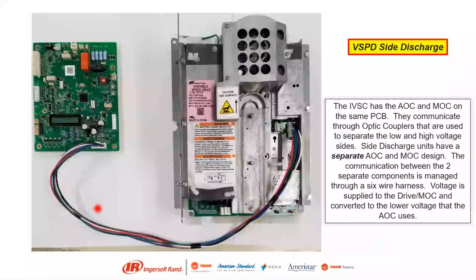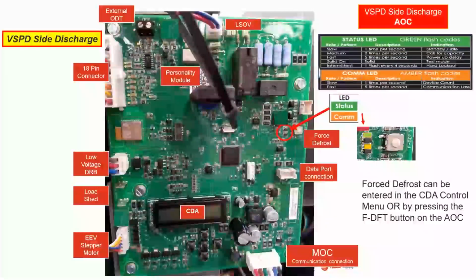Sometimes we get a bad harness, so we want to always double check these connections. With the power off, I like to pull these connections, put them back in, and then push the wires all the way in to make sure we got a good solid connection. Here's our board. Here's our CDA, EEV stepper motor, our voltage. So we'll have test pins right there, 18-pin connector with all of our sensors. I'll go into that. Here's our personality module, our switchover valve, reversing valve. We can force a defrost if need be from button or go cycle through our CDA.